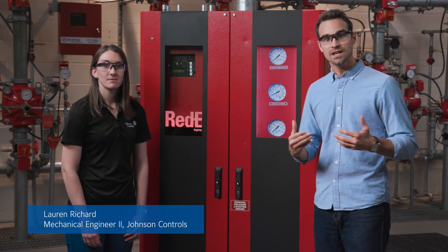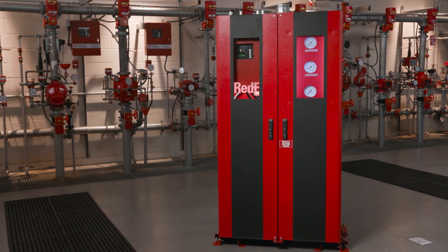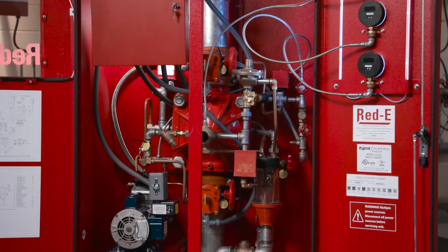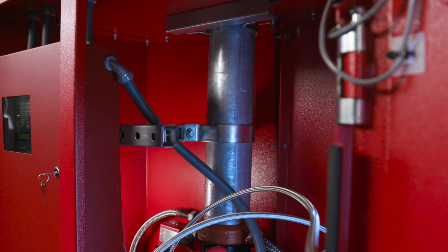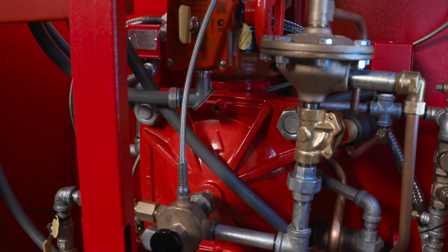To begin with, can you tell me generally about the cabinet? Sure. The Red-E Cabinet is a pre-assembled fire protection valve package enclosed within a freestanding cabinet. It requires minimal floor space and offers a nice-looking enclosure for a fire protection valve riser. It readily incorporates one-and-a-half to eight-inch valve risers — DN40 to DN200 — for a series of options for deluge and pre-action systems. Here, we're showing a pre-action double interlock system with an electric pneumatic actuation.